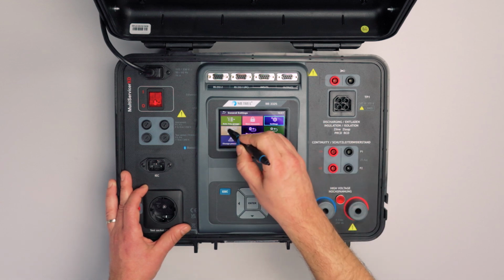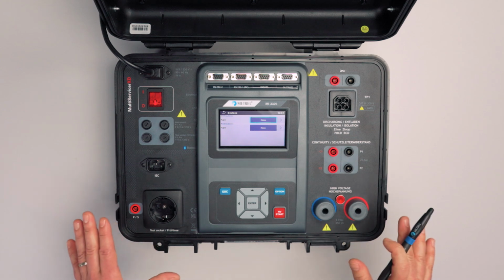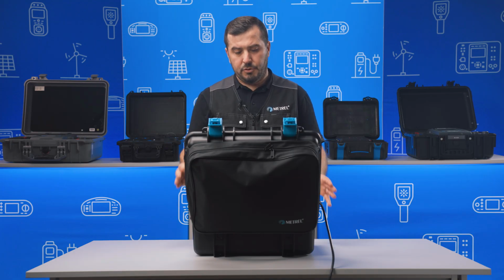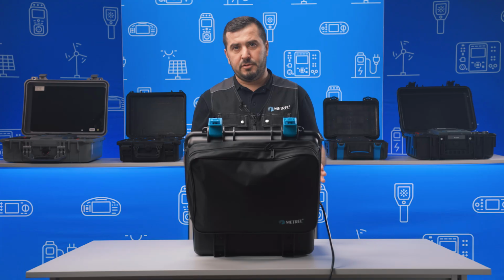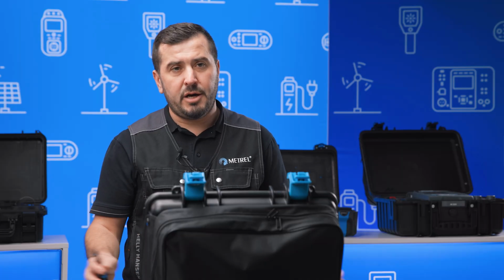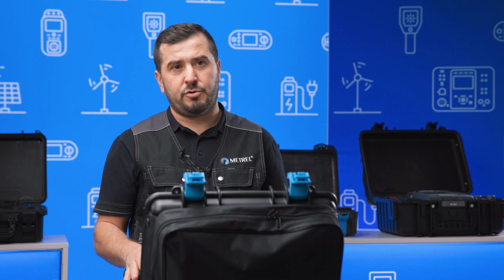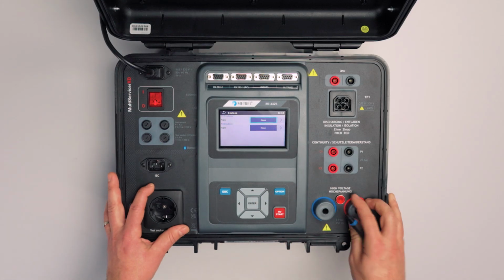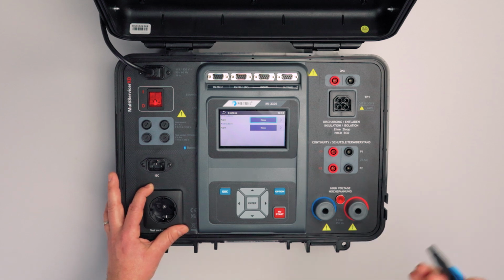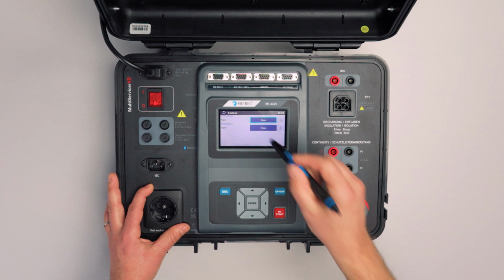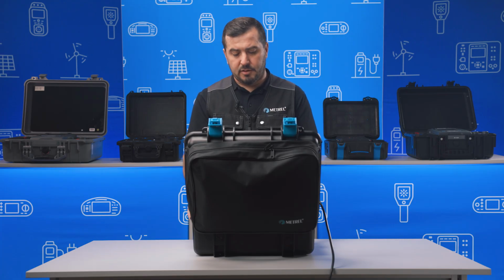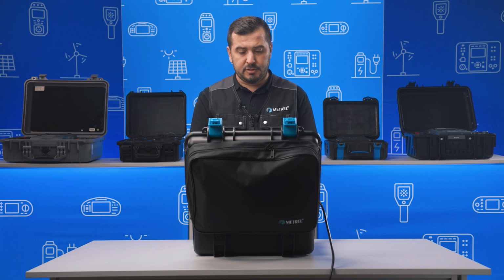Then the next menu here is the devices. So the instrument itself also supports a few optional reading and writing devices. Those devices come in two options, wired or wireless. So the instrument enables you to connect via Bluetooth or via serial communication port different devices like scanners, printers, NFC readers. Okay, the next option here is the Bluetooth initialization. In case that some problems happen between communication, we can simply initialize the Bluetooth module and the communication will be established again.